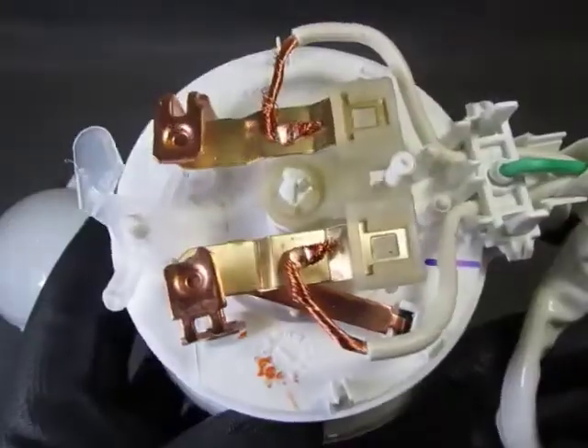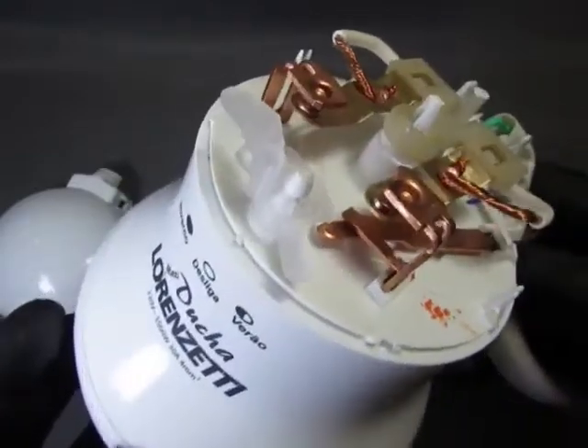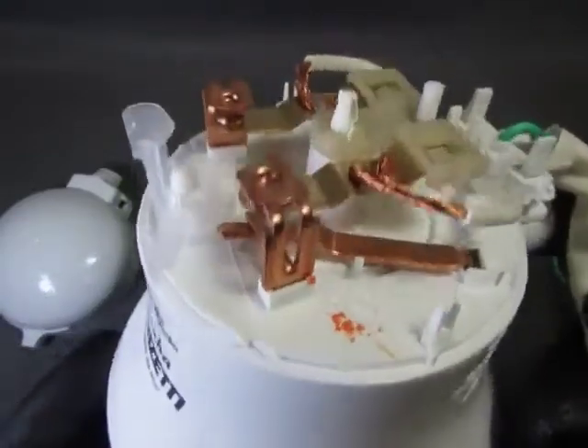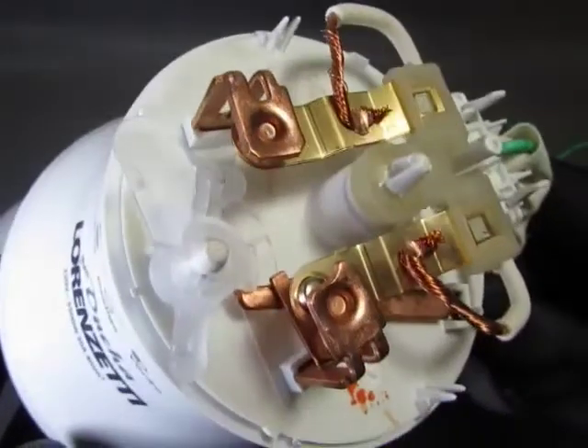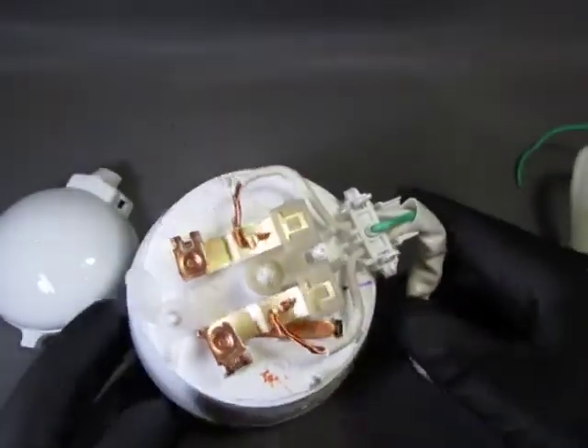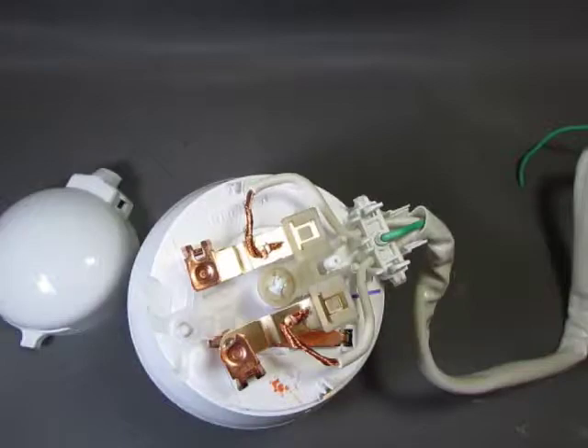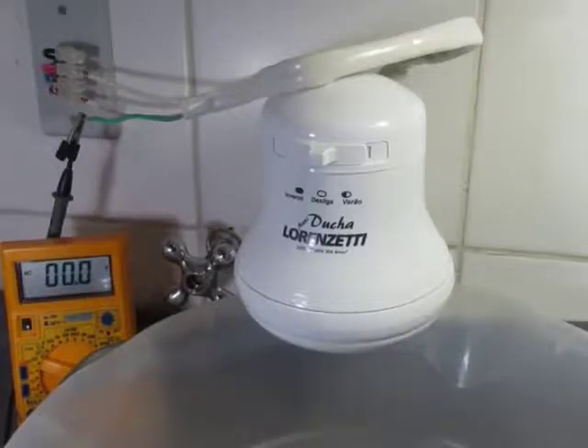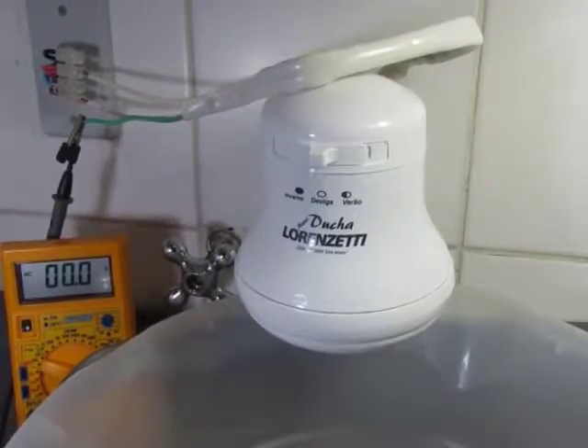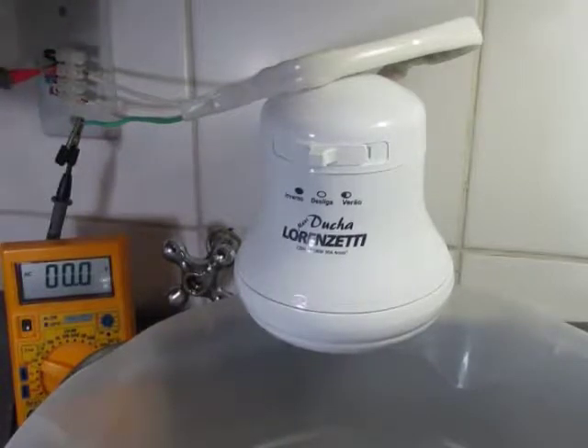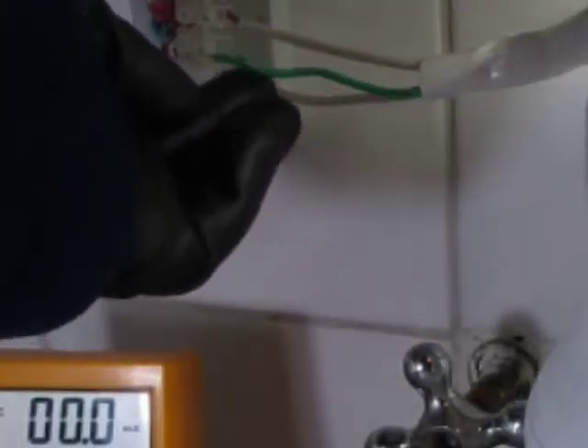Good old Ohm's law. We will run our tests with our temperature switch on the lower temperature position because our circuit breakers are only capable of 20 amps and I am not interested in testing the shower for power but for grounding safety. Well, here at BSFEEChannel we have a convenient setup for testing our shower head. We have a two-phase 220 volts connection and a ground connection. This blue wire here is the neutral and it is not going to be used. We will leave the ground wire disconnected for the voltage measurements.